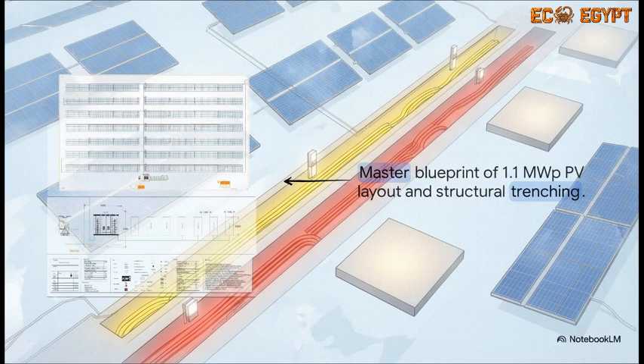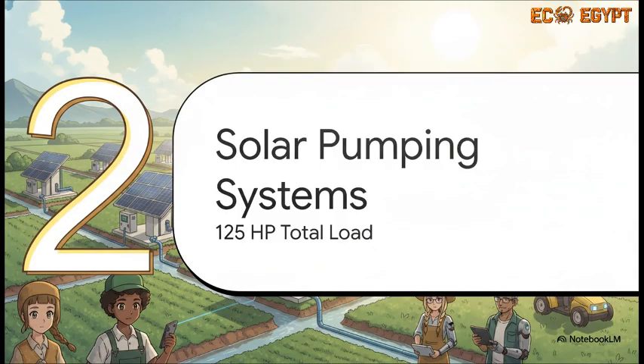The civil engineering is absolutely rigorous too. Your DC and low-voltage trenches must maintain a strict 500mm horizontal separation. Plus, to prevent catastrophic mistakes during future maintenance, they use buried color-coded warning tape, yellow for DC cables and red for LV cables. It's exactly this level of granular detail that prevents absolute disasters on site. Moving right along to Section 2, solar pumping systems.